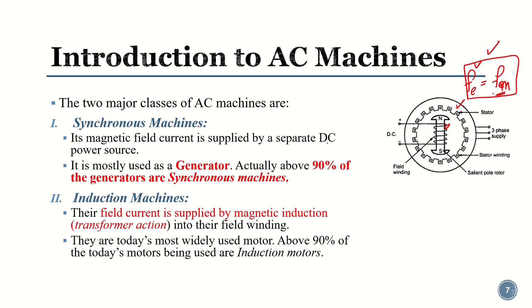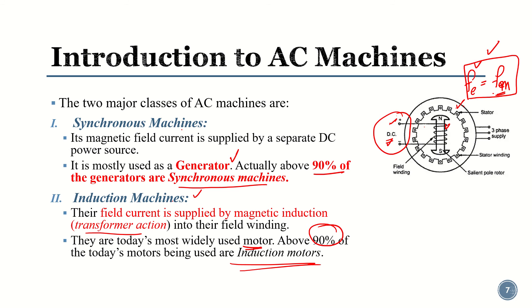This principle is practically used in generators — 90 percent of generators are synchronous generators. In induction machines, the field current is supplied by magnetic induction, a transformer action. In a synchronous machine you supply the field current via a separate DC power source to the rotor; in an induction machine you do not use a separate DC input source — it happens through the induction process, which we will see in more detail later. This principle is mostly used in motors, as 90 percent of motors are induction motors.